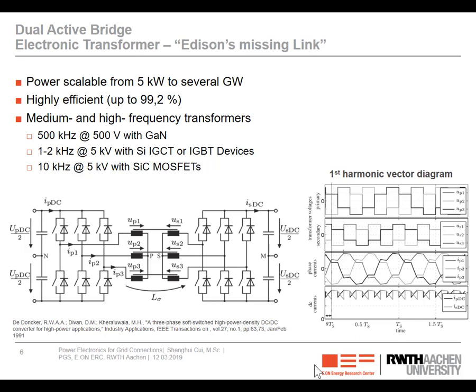Like the converter we will see tonight in our test hall, it is designed for 5 kV voltage rating and 7.5 megawatt power rating, and the transformer used in this converter is operating at 1 kilohertz. And if you use silicon carbide technology, then even in the medium voltage range, the frequency can be elevated to as high as 10 kilohertz.